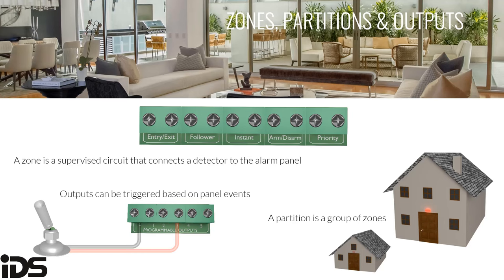A partition is a group of zones that may be controlled independently from any other group. Partitions have their own separate settings, allowing them to act completely independently. For example, you could have your house as partition one and your perimeter as partition two. In a business, each department can have its own partition armed and disarmed independently based on its staff. When programming, global settings affect the whole panel, while partition settings only affect the partition being programmed — so you can have different siren durations or user access per partition.